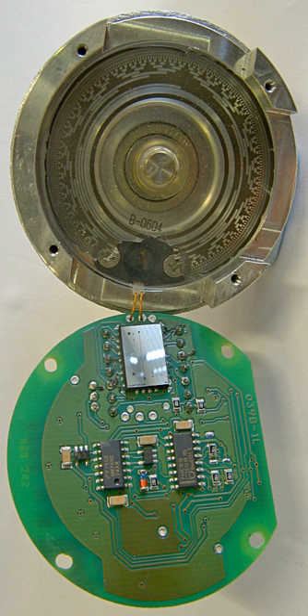Topic: Data output methods. Depending on the device and manufacturer, an absolute encoder may use any of several signal types and communication protocols to transmit data, including parallel binary, analog signals, current or voltage, and serial bus systems such as SSI, BiSS, DeviceNet, Modbus, Profibus, CANopen and EtherCAT, which typically employ Ethernet or RS-422 or RS-485 physical layers.